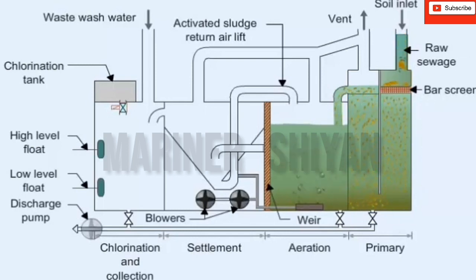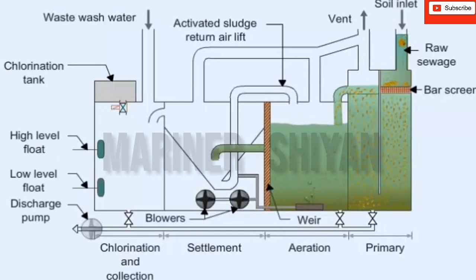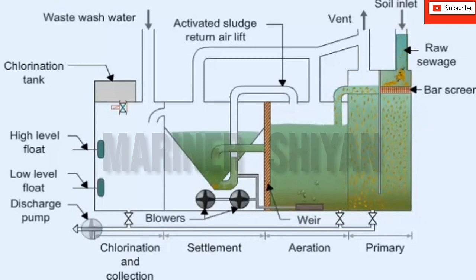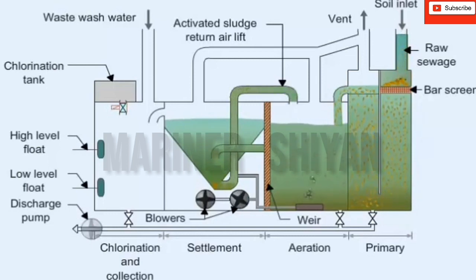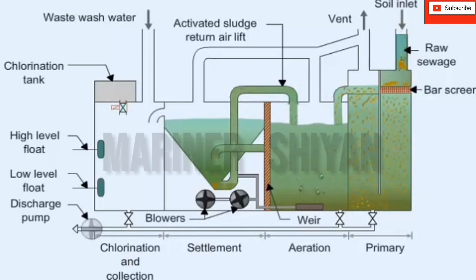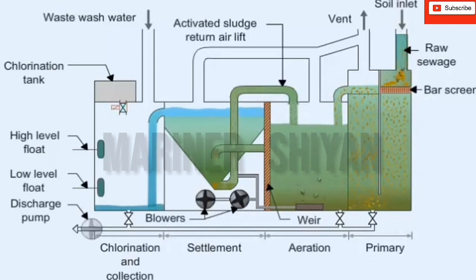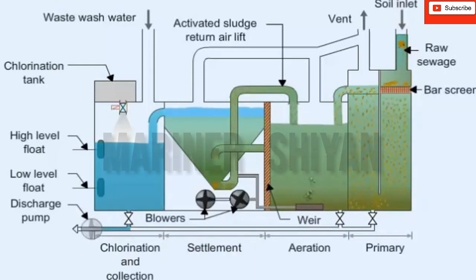After prolonged aeration, the mixed liquor is displaced into the settlement tank where the biological floc is formed. Activated sludge gravitates to the bottom and is continuously withdrawn and returned to the aeration chamber to mix with incoming waste. In the unit shown, the sludge is returned to the aeration compartment by an airlift. Clean effluent from the top of the settling tank is collected in the last compartment for disinfection and discharge overboard.